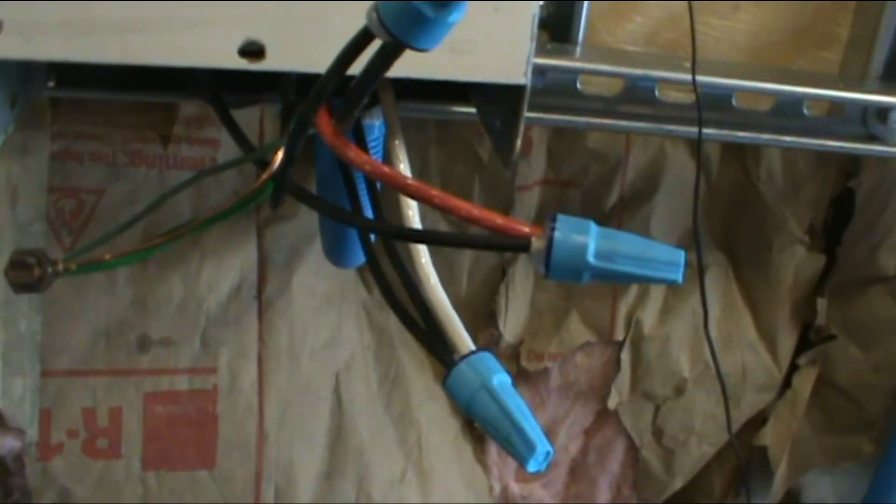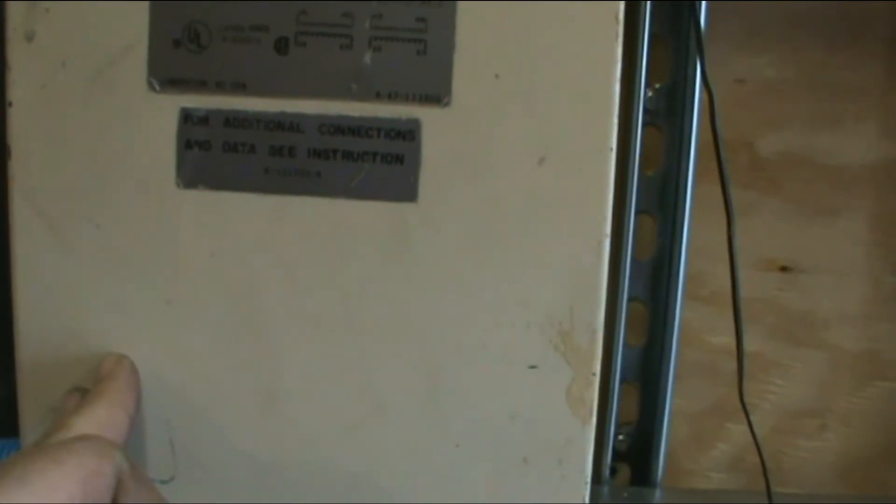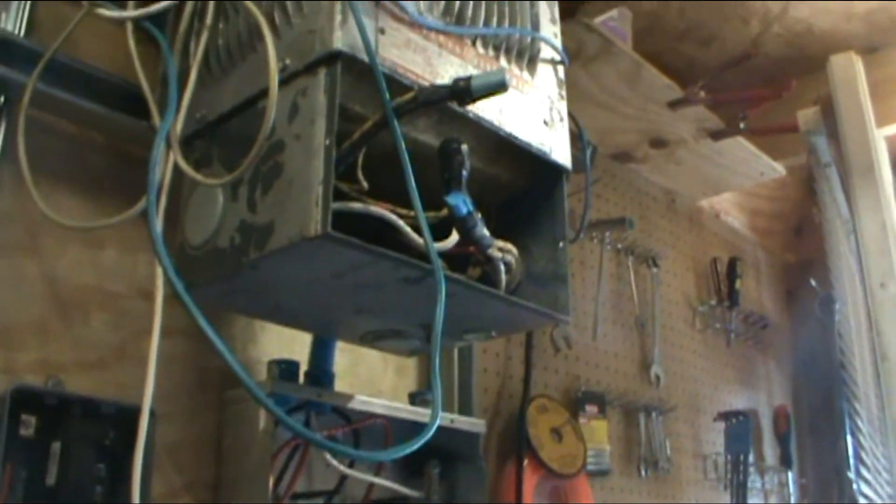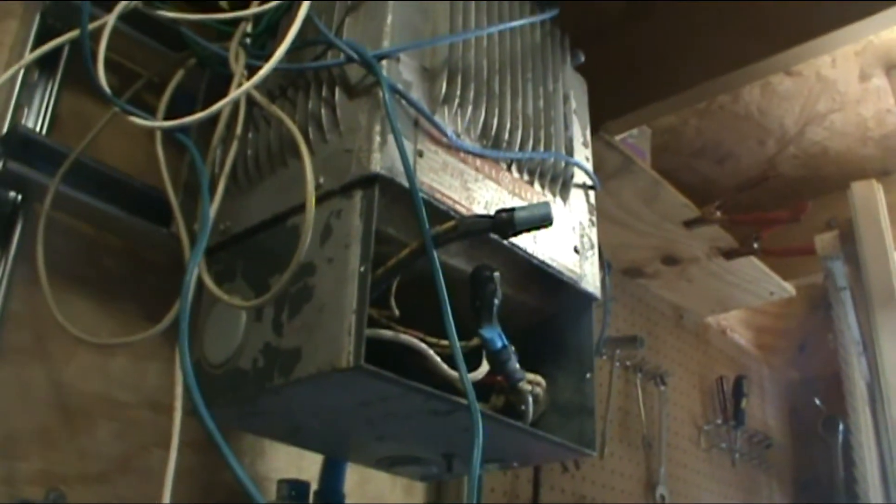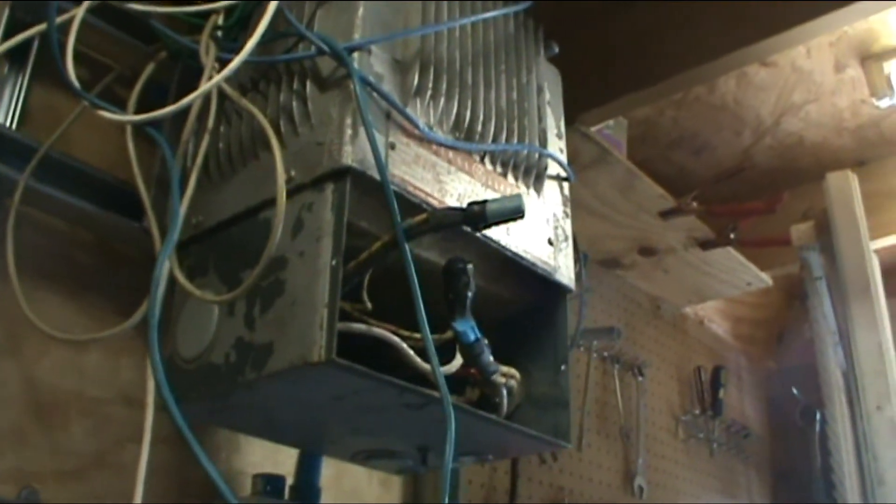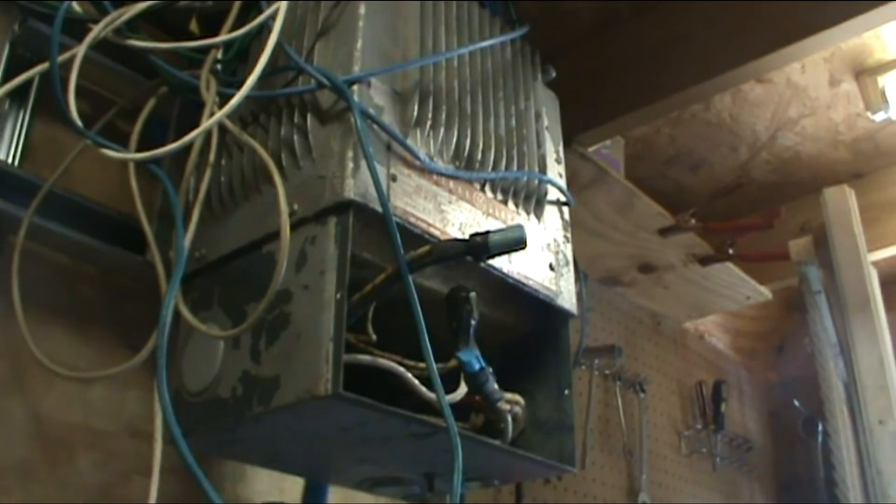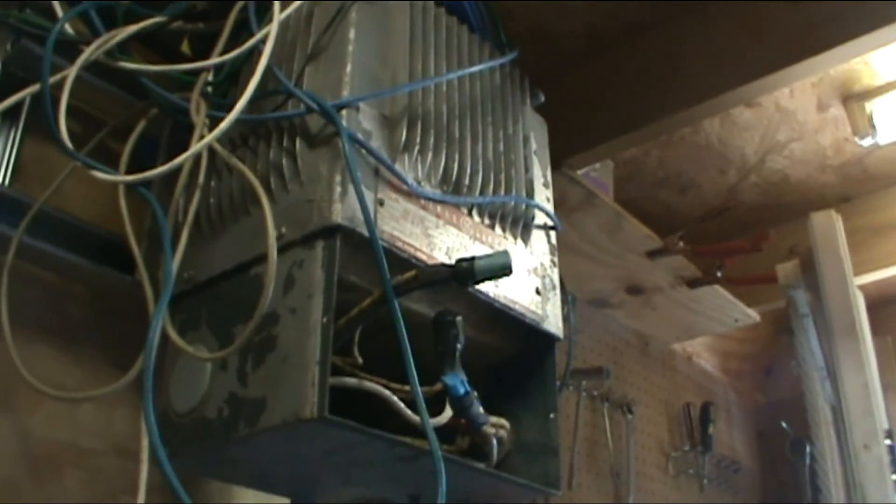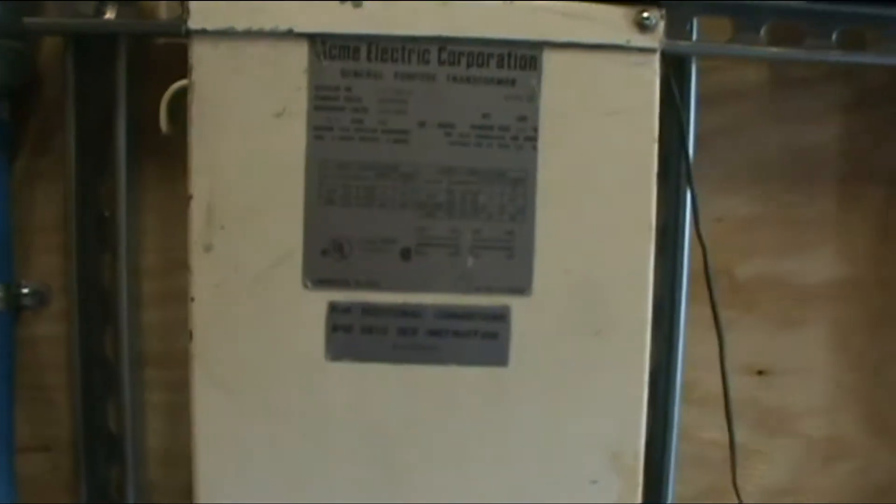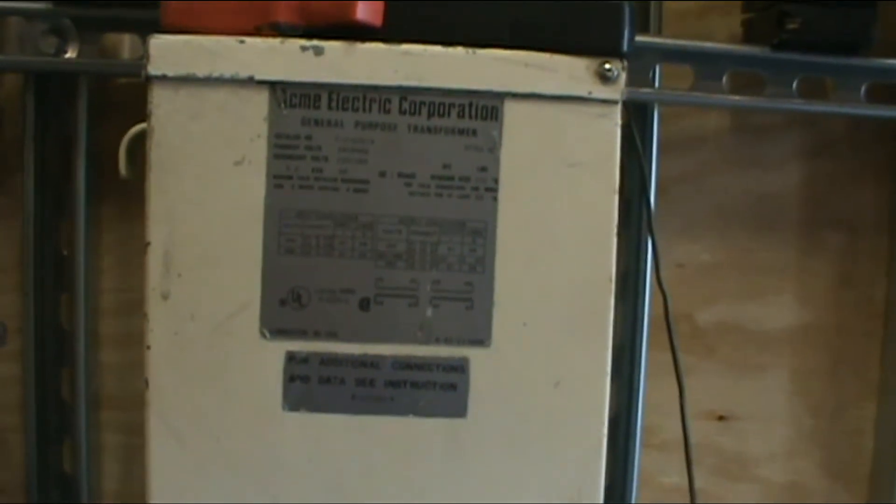I hope this answers any questions on how this stuff's wired up. This transformer just on standby uses anywhere between 50 to 100 watts by itself, depends on how cold it is. About 100 watts by itself, about a half amp at 240 volts. It's really not bad. That one there uses 200 to 240 watts. I looked these transformers up, this one uses aluminum.